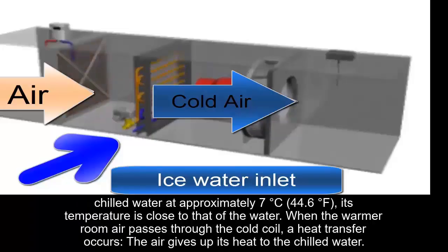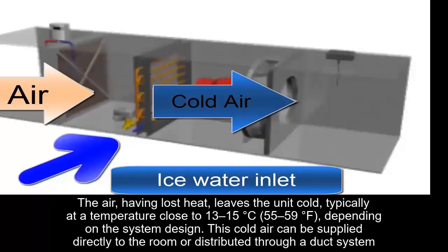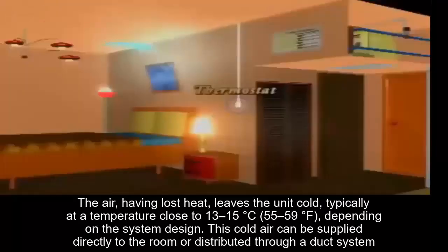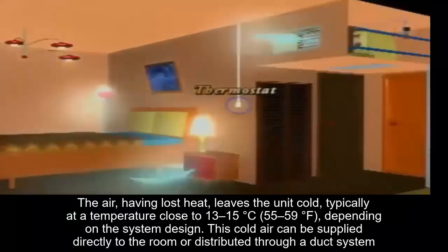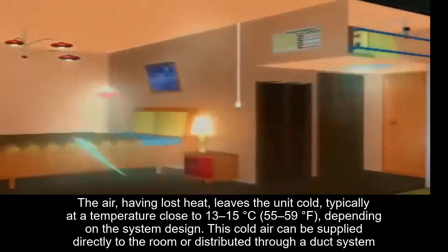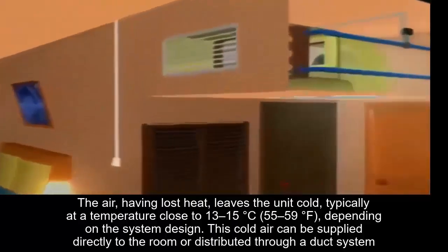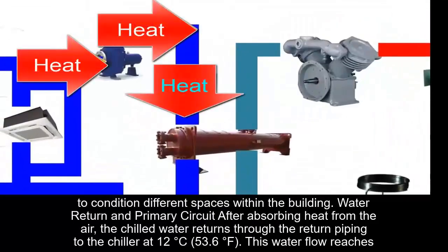Since the coil contains chilled water at approximately 7 degrees Celsius or 44.6 degrees Fahrenheit, its temperature is close to that of the water. When the warmer room air passes through the cold coil, a heat transfer occurs. The air gives up its heat to the chilled water. The air, having lost heat, leaves the unit cold, typically at a temperature close to 13 to 15 degrees Celsius, or 55 to 59 degrees Fahrenheit, depending on the system design. This cold air can be supplied directly to the room or distributed through a duct system to condition different spaces within the building.